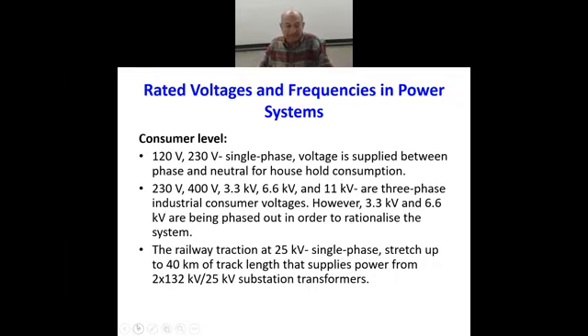In the distribution systems, as you can read, there is the 230 volt three-phase system in the United States or Japan, and 400 volt or 410 volt three-phase distribution system in our country, or in most of the countries in the world. They follow the single phase consumer voltage of 230 volts. Then earlier, the power was distributed at 3.3, 6.6, and also at 11 kV level.